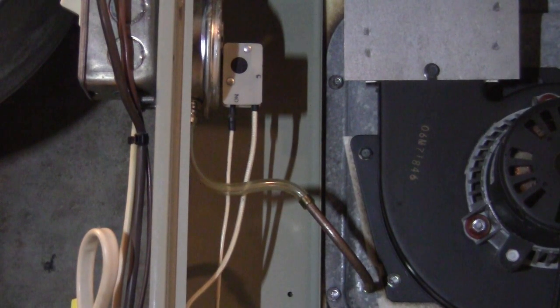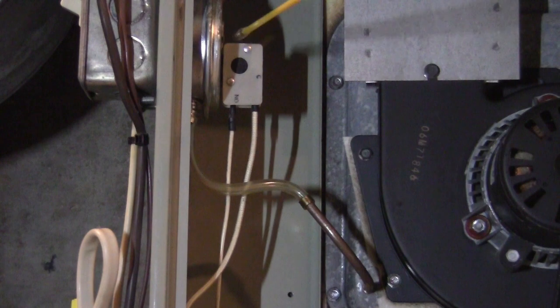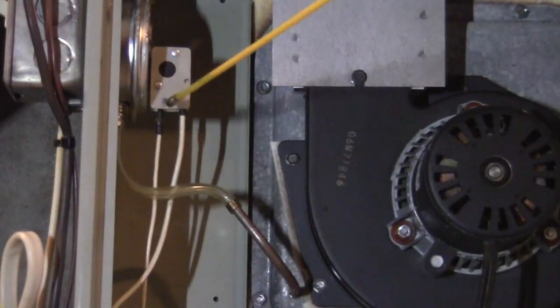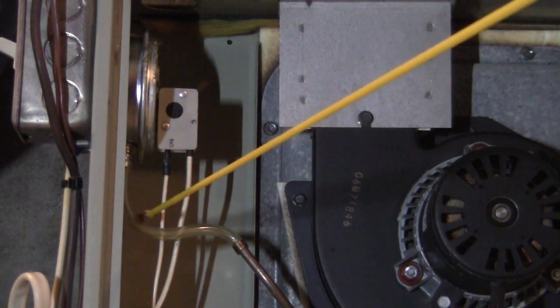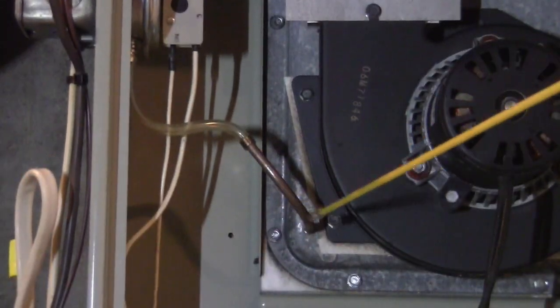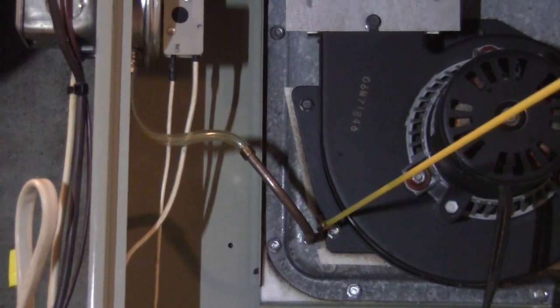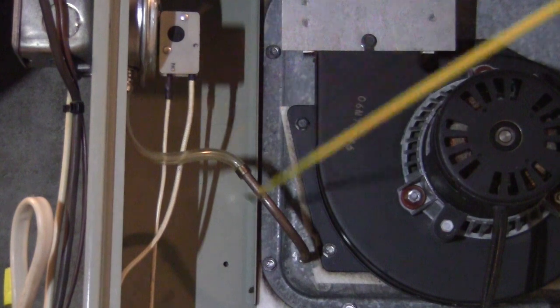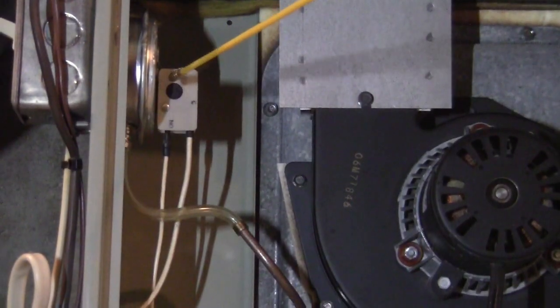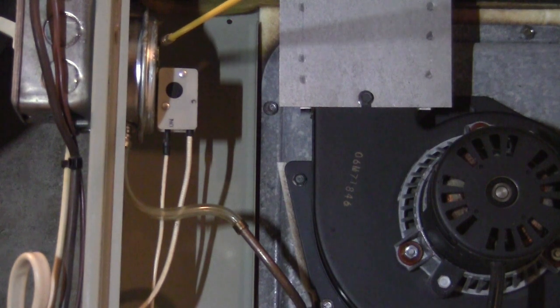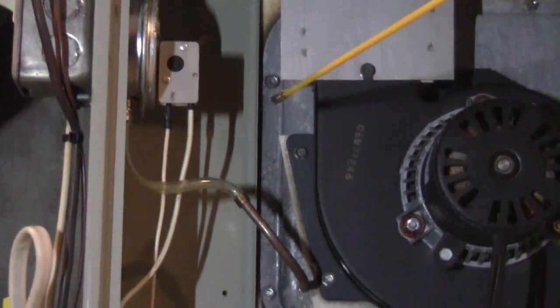But how does the controller know the fan is working? The controller does not detect whether the fan is spinning or whether the fan is drawing any current. Actually, the controller uses this valve. This is called a pressure valve. Using this valve over here, there is a connector connected to the inside, and this has to be airtight. This valve is actually something like a vacuum valve. The theory is very simple.